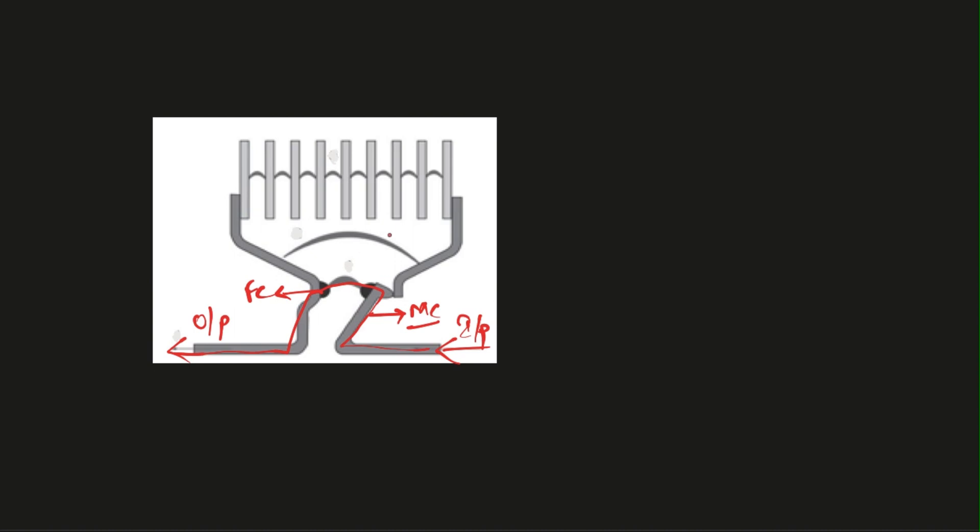When this moving contact and fixed contact are separated due to some faulty condition, then an arc is created between them. When there is a gap created between them, air starts to flow. Because this arc is at higher temperature than the normal air, this arc starts to move in an upward direction.